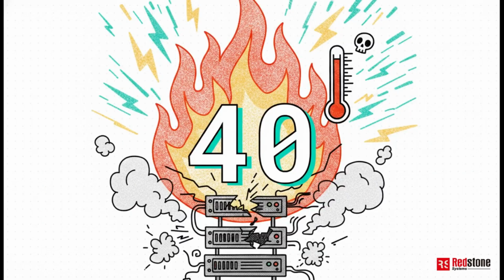I really want you to lock this number in your head right now, 40. That's 40 degrees Celsius. It is the absolute maximum limit your equipment can endure before the ambient heat becomes a critical threat. If your room's air conditioning fails and that temperature creeps past 40, your hardware is essentially baking in a sauna. At that point, unexpected system shutdowns or permanent costly hardware damage are practically guaranteed.